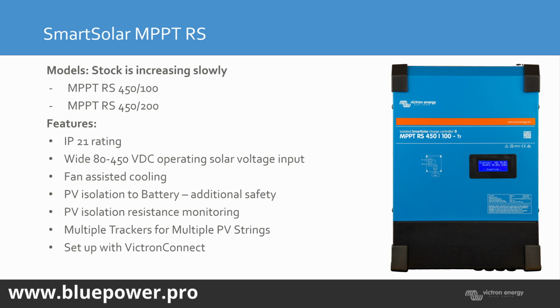There's a nice high voltage MPPTs, with very high efficiency. And yeah, they've got active cooling. They're not like the old MPPTs which have got natural cooling. They've got fans built in, so they have to be serviced as well. And it's got an isolator switch built in on the unit, and PV connections. No, these ones don't, sorry, for the PV connections. The Multi-RS has the PV connections, and the MPPTs just have normal screw terminal connections for your PV.